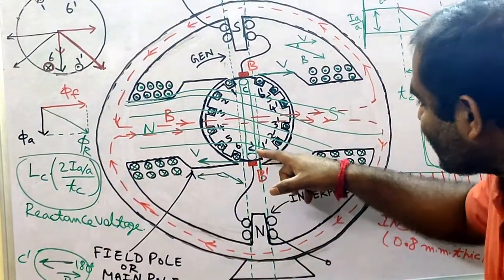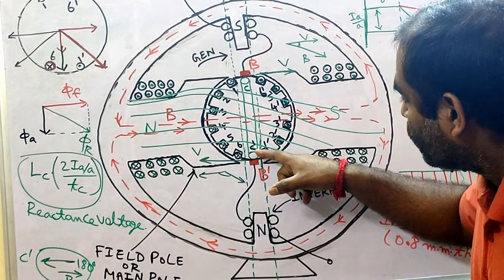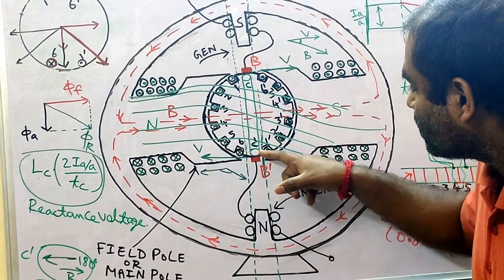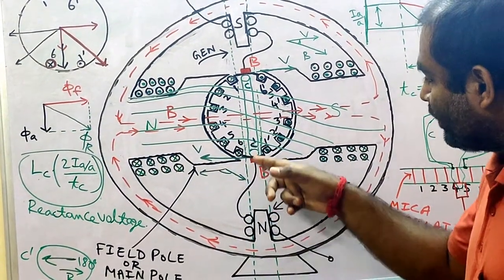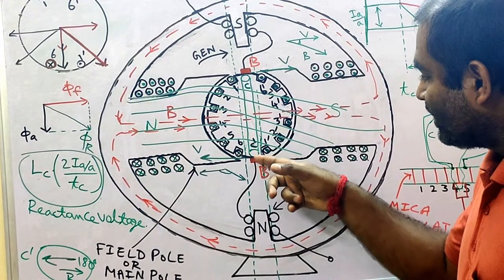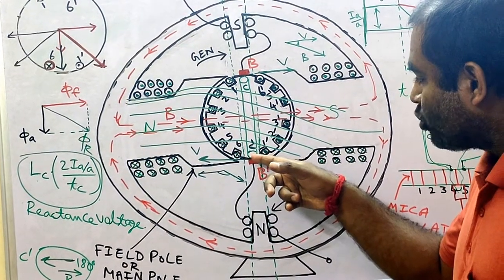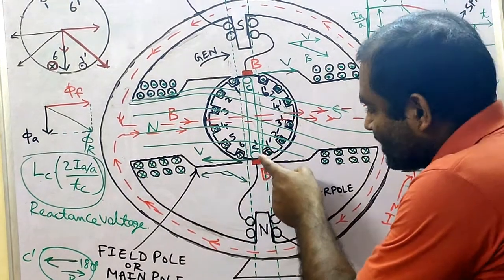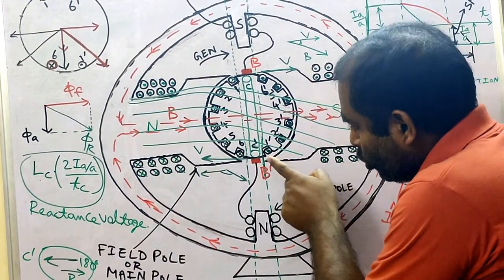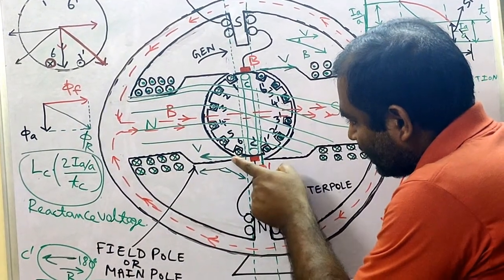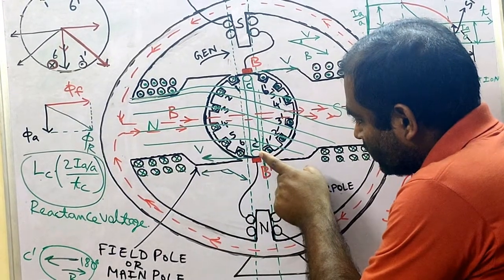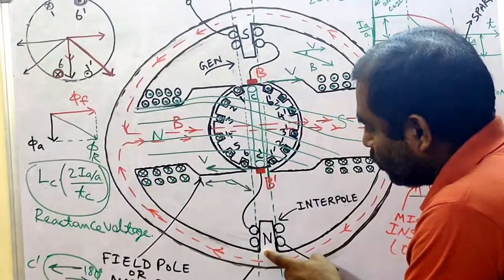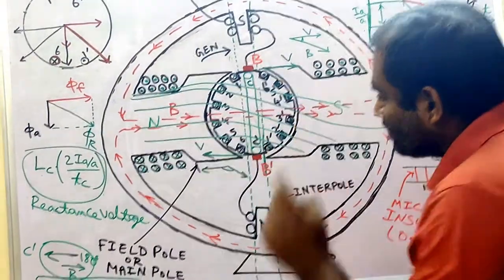So this interpole is a south pole, and obviously the other interpole will be a north pole. Applying the same logic: coil side C' is going to move to the position previously occupied by coil 6, where it will attain cross polarity. So this interpole should induce cross polarity in coil side C'. The interpole polarity is determined by what polarity the commutated coil needs to attain after commutation is complete.